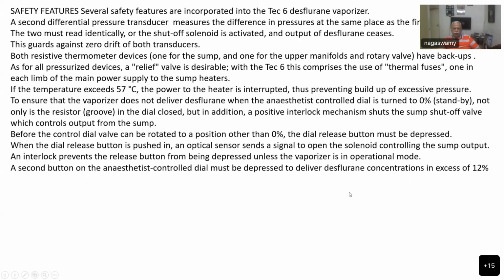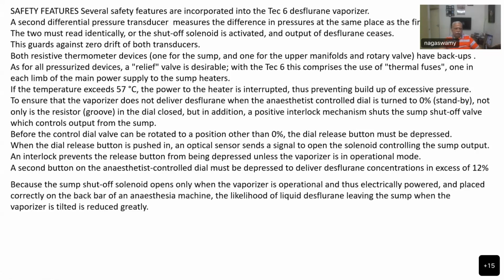So from 0 to 10%, you have one press of the button, and beyond 12%, it needs to be pressed again. And because the sump shut-off solenoid valve opens only when the vaporizer is operational, and thus electrically powered and placed correctly on the back bar of the anesthesia machine, the likelihood of liquid desflurane leaving the sump when the vaporizer is tilted is reduced greatly. So the tilting mechanism will not make the liquid get spilled into the vaporizing tubes.